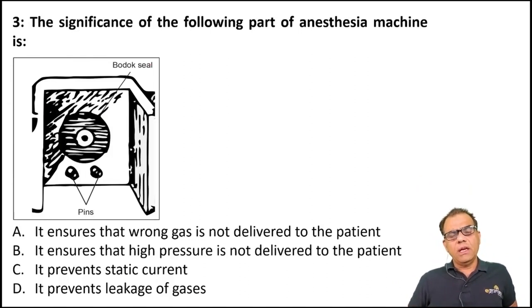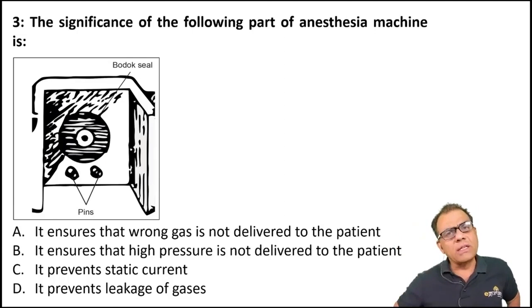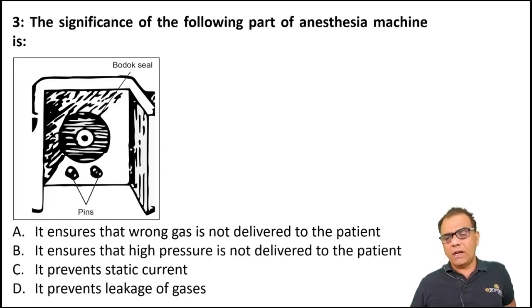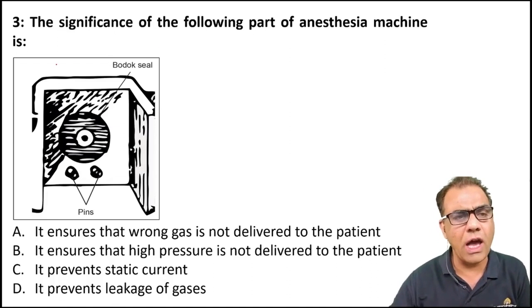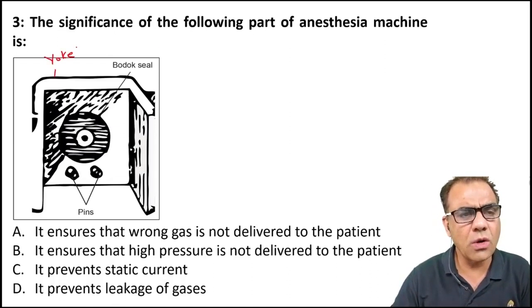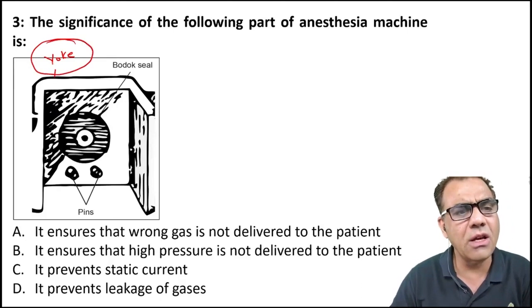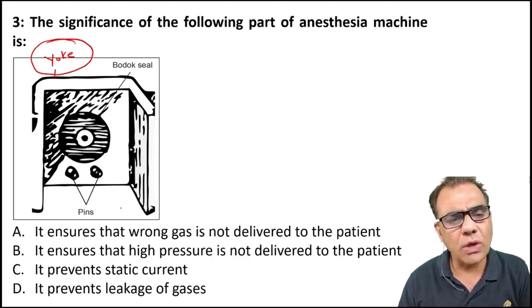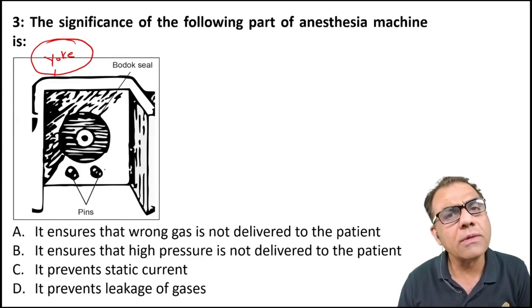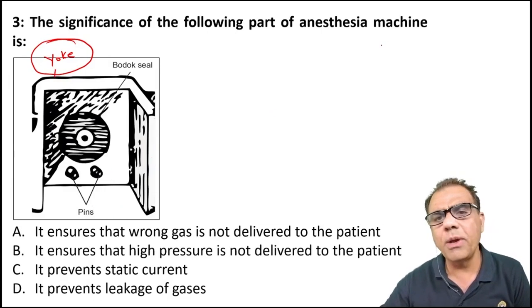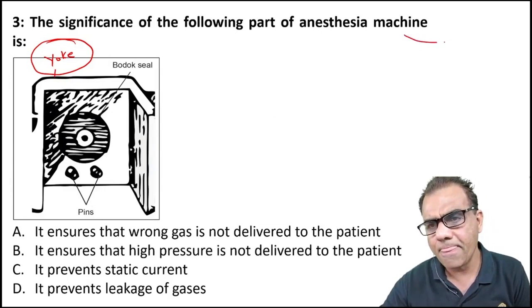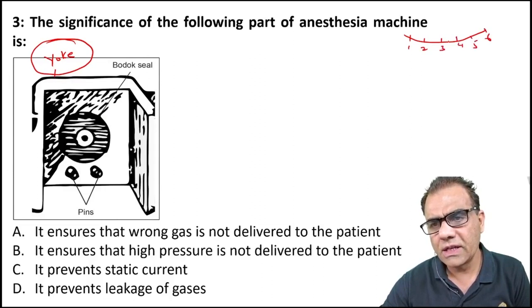So the pin index system is not only part of the cylinder, it is part of the cylinder as well as the anesthesia machine as a combination. So more or less it is a part of the anesthesia machine. And the part of the anesthesia machine which contains this pin index system is called the yoke. So this is the yoke. The yoke is that part of the anesthesia machine where cylinders are fitted. So it has the pin index system. It has two pins. There are 7 pin positions which have been described. 1, 2, 3, 4, 5, 6, 7.